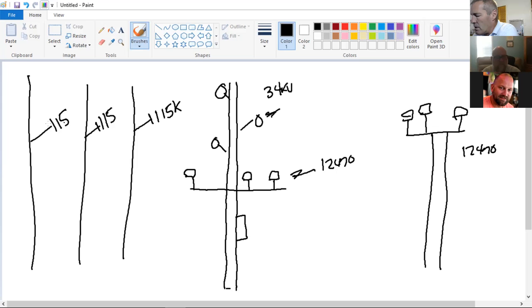Now, the question has come up before: am I having magnetic induction now from these sets of lines? Is magnetic induction happening? Let me back that up - is each one of these phases making a magnetic field? It's energized and has amperage on it, so yes, it is. But if these other lines are all energized too, guess what they're doing? The same thing - they're doing the same thing. This is called bucking. They're actually not getting any induced voltage because they're creating their own magnetic field, which forces the other magnetic field away. Same on these conductors down here. So there's no magnetic induction going on.